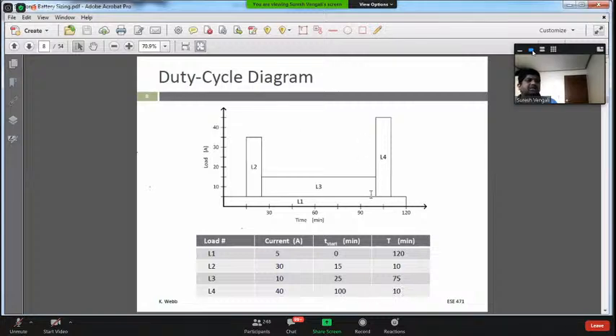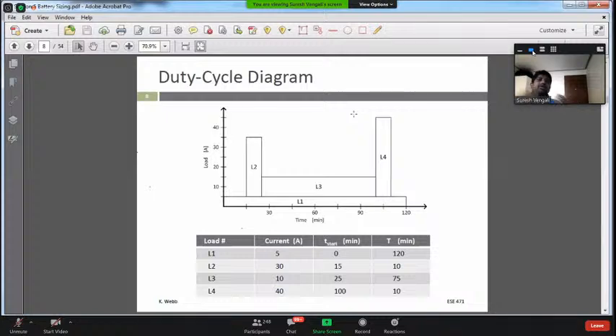This is not correctly mentioned - sometimes this is a 1 minute, sometimes they will mention it differently. So like this much feeding is very high, like 40, but this is just example one. When you see the real time, you need to apply 400 amps for 1 minute. 400 ampere - how will you supply it? You need to have a load bank, and how big a load bank you need again. So it will supply transient loads, but this is the criticality - the problem is your battery size will increase a lot.